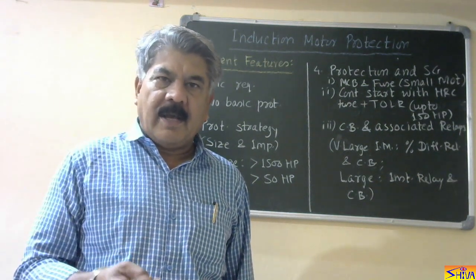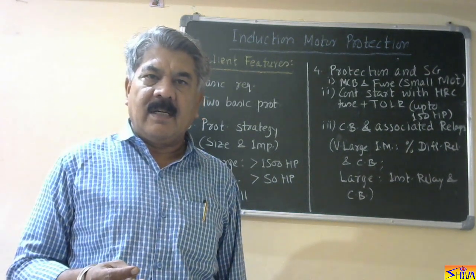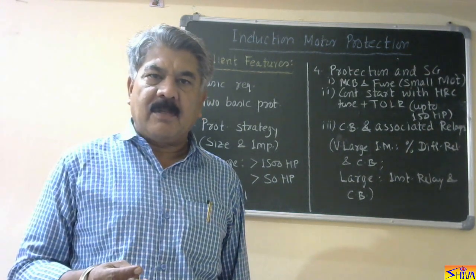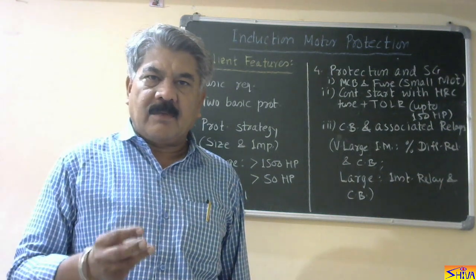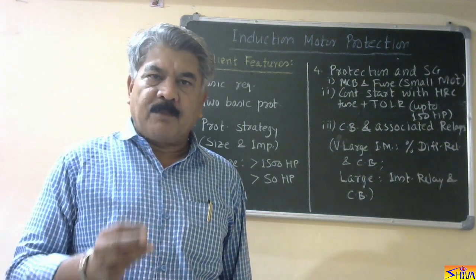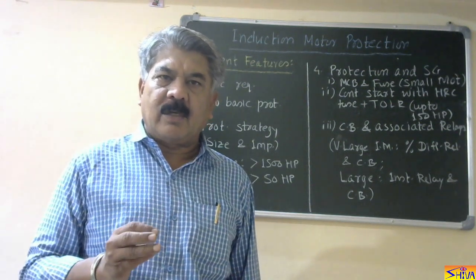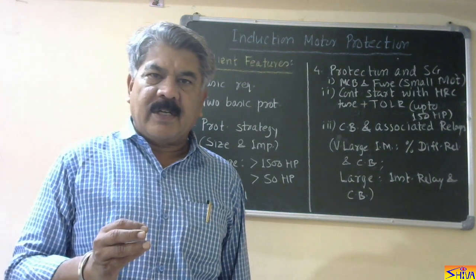Number one, as you know, when induction motor is started, it draws heavy current, that is up to 6 to 8 times the full load current. So first requirement is during starting, the protection scheme should not operate. During starting, as the induction motor is drawing heavy current, the protection should not operate.